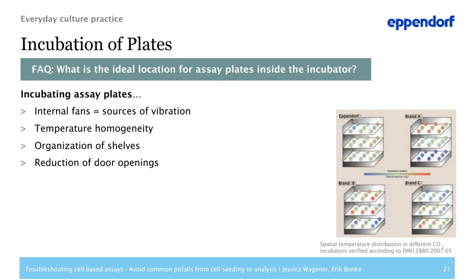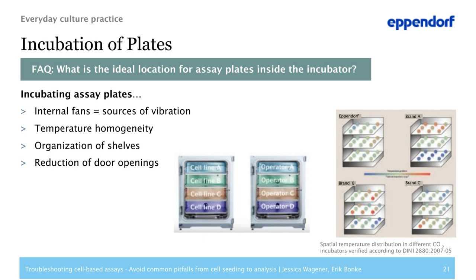Does it make any difference if plates are placed on different shelves or incubated in the back versus the front of the shelf? When your incubator has a fan inside, this can be a source of vibration. Temperature homogeneity measurements show that some incubator models show quite high temperature variation depending on shelf position and location on the shelf. A performance check using external temperature probes can reveal if incubators in your lab show temperature deviations that are critical for the cells. Organizing the shelves helps reduce door-opening duration.